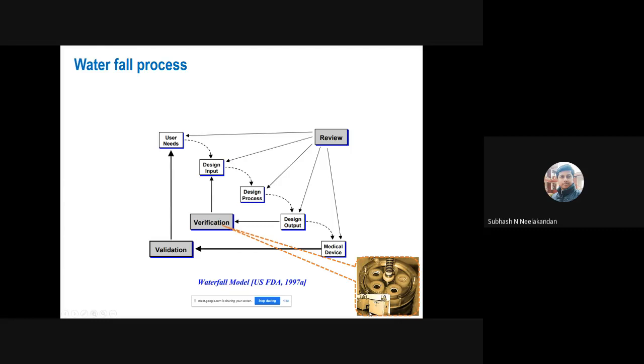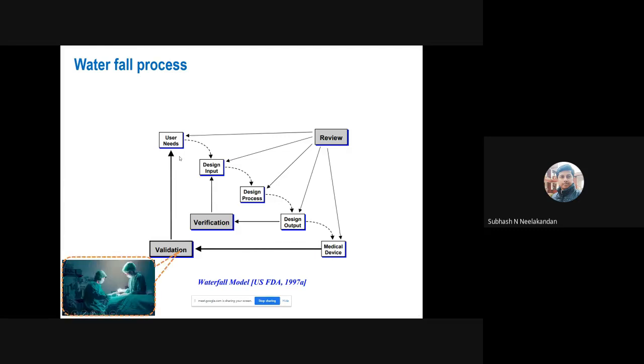So have a look here. This is again the accelerated test setup which we have used for testing hardware. If the device design is passing this particular test, it means that our device meets the design input. That means the design input is met, but we are not sure whether it is working properly inside the human body. So for that, we need to do a validation. The validation says, yes, the device is meeting the clinical requirements also. So that is basically the difference between verification and validation.